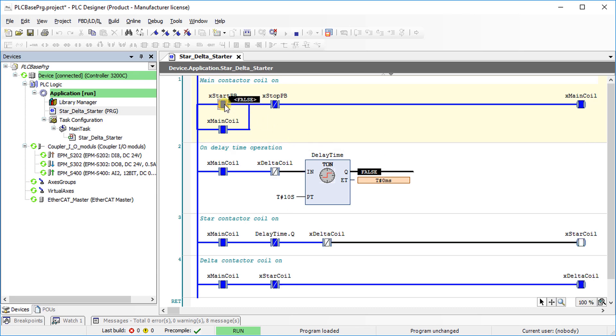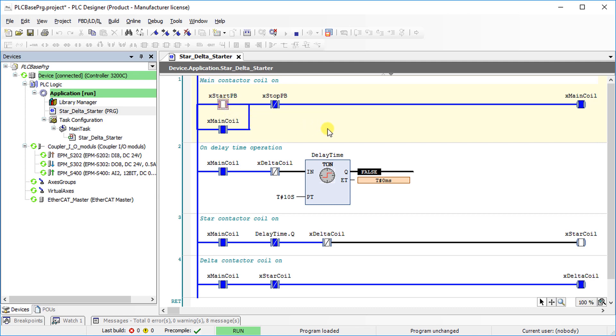On delay timer starts counting as soon as the main coil turned on. Now, change the state of X start PB to make it false. Contact and coils have been highlighted in blue means, they are in logical high state. After the delay time is over, star coil turns off and delta coil turns on. Main coil remains on.